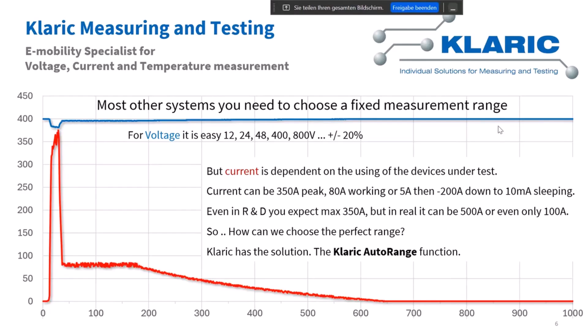But when I choose the wrong range, it is a little bit like I zoom out. I cannot see all the details that much anymore, and therefore I also lose accuracy of the system. This means I can see less of the behavior of my devices under test. This is, of course, not so good. And on the other side, when I choose too small a range, then I'm losing data because I come into the over range, and then maybe I need to do my test again and so on. So this is the problem when we measure current in this kind of situation: we don't know the current, and therefore this is quite difficult.